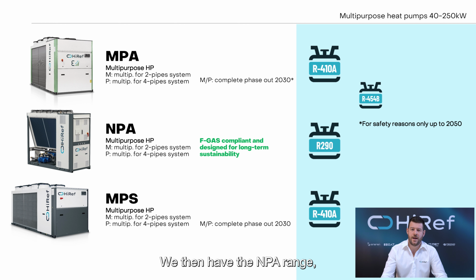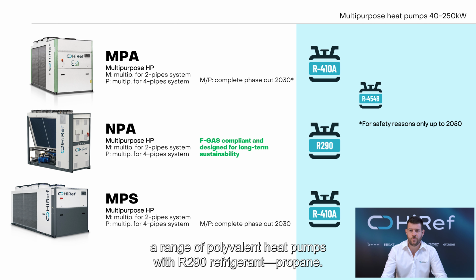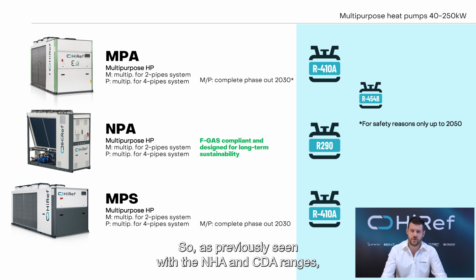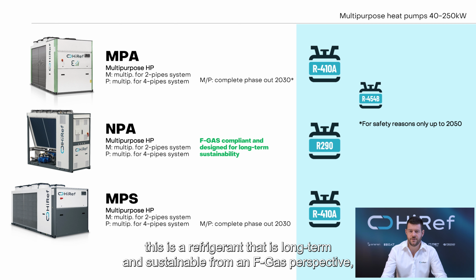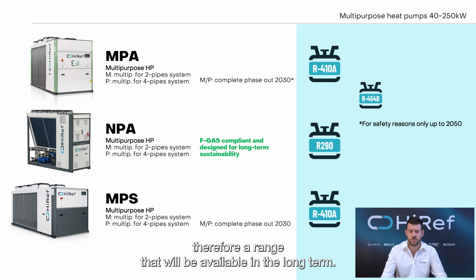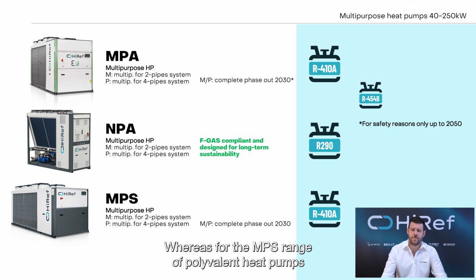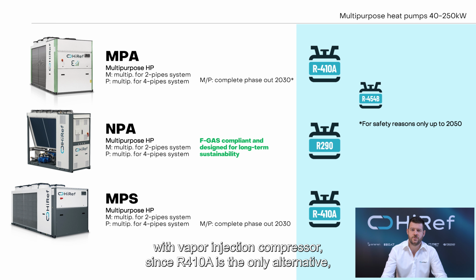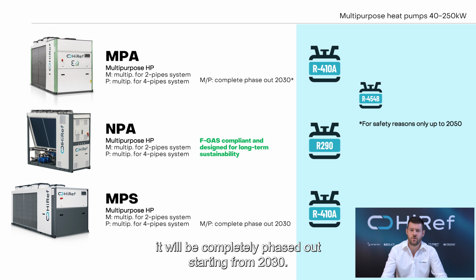We then have the NPA range, a range of polyvalent heat pumps with R290 refrigerant, propane. So as previously seen with NHA and CDA ranges, this refrigerant is long-term and sustainable from the F-gas perspective, therefore a range that will be available in the long term. Whereas for the MPS range of polyvalent heat pumps with vapor injection compressor, since 410A is the only alternative, it will be completely phased out starting from 2030.